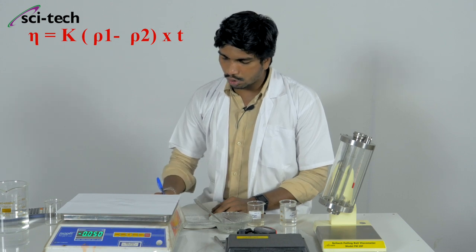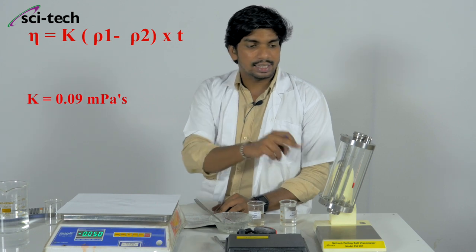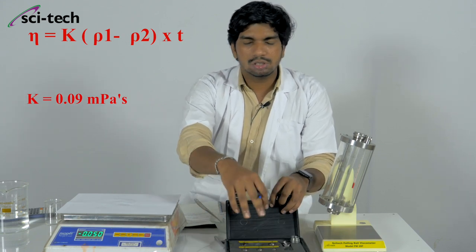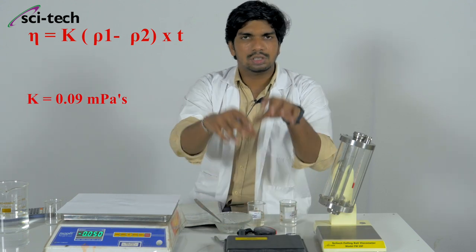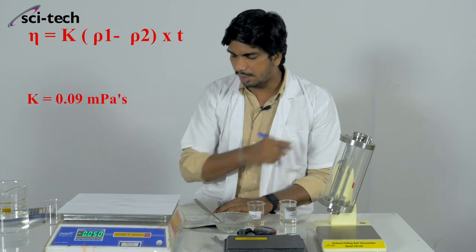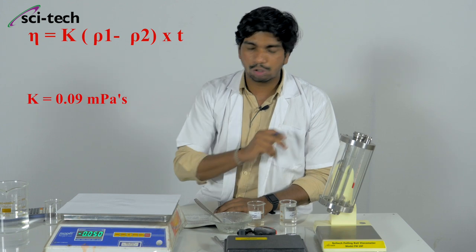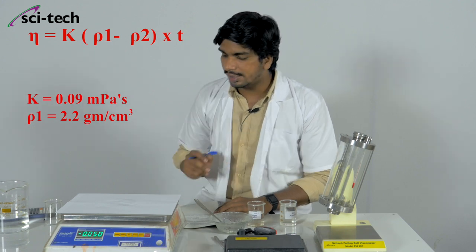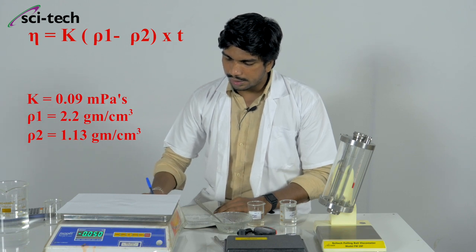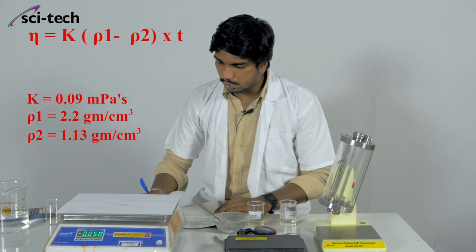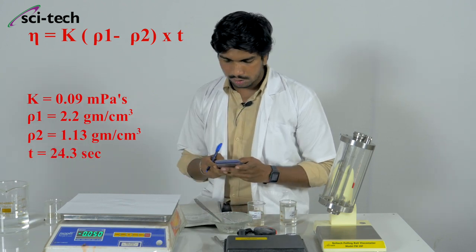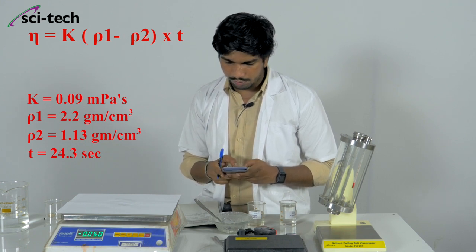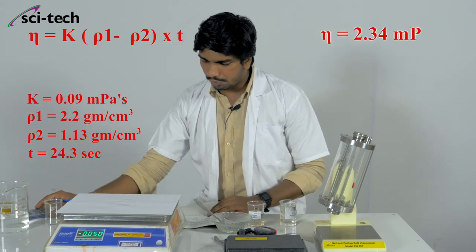For the 40% sugar solution: density of the ball is 2.2 g/cm³, density of the solution is 1.13 g/cm³, ball constant K for ball number 2 is 0.09 mPa·s·cm³/g, and the mean falling time is 24.3 seconds at a measuring temperature of 30°C. All 6 ball constants and densities are given in the manual. Calculating: 0.09 × (2.2 − 1.13) × 24.3 = approximately 2.34 mPa·s dynamic viscosity.